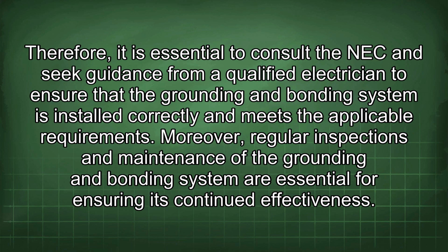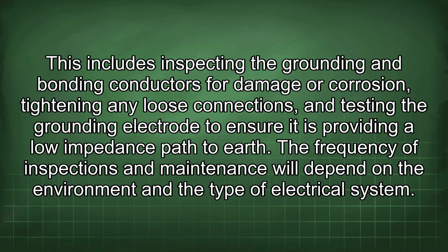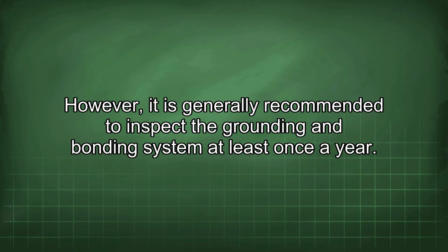Moreover, regular inspections and maintenance of the grounding and bonding system are essential for ensuring its continued effectiveness. This includes inspecting the grounding and bonding conductors for damage or corrosion, tightening any loose connections, and testing the grounding electrode to ensure it is providing a low impedance path to earth. The frequency of inspections and maintenance will depend on the environment and the type of electrical system. However, it is generally recommended to inspect the grounding and bonding system at least once a year.